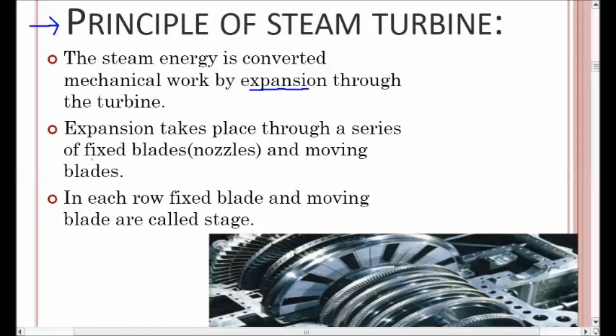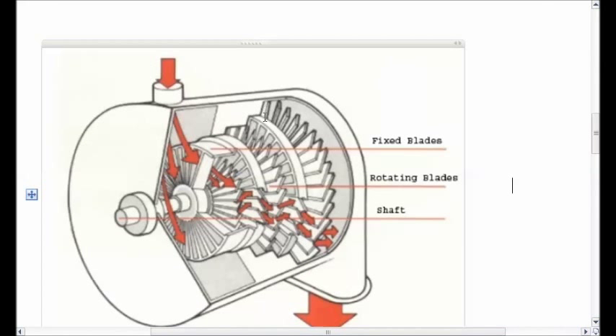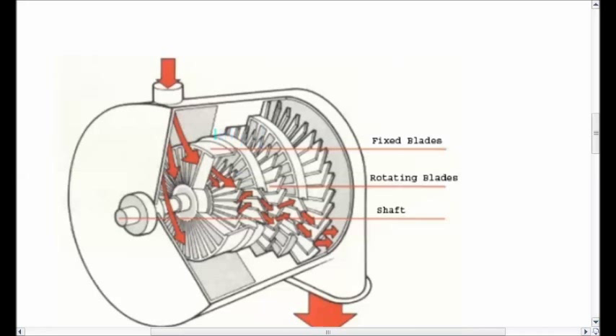In a steam turbine there are two major components for converting energy into rotary motion: the fixed blade and the moving blade. Fixed blades are also called nozzles. In each row, a fixed blade and moving blade together are called a stage. The components that don't move are called fixed blades, also known as the stator, while the components that move are called rotating blades, also known as the rotor.